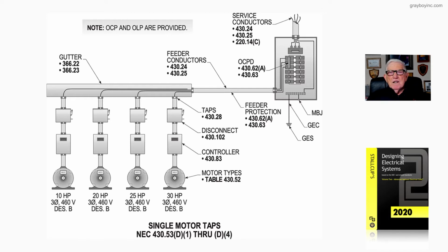If you're on the supply side, as you see the breaker here, which says service conductors, then that's 230.82 on page 95 of the code. That's where you'd pick up the taps there, and of course they're all listed there. But notice service breakers and taps and switches, they're not going to be listed there because that's in Article 230, so that you'd pick that up. So don't get mixed up on that.